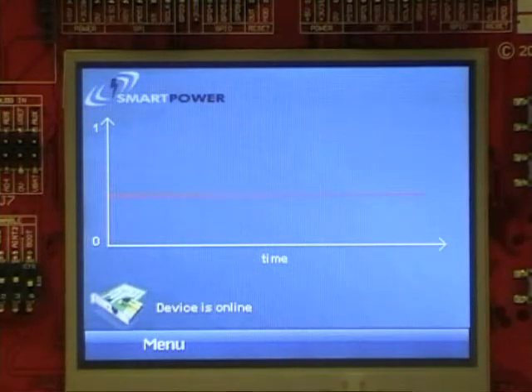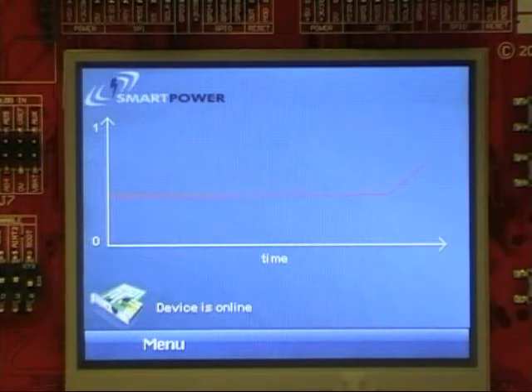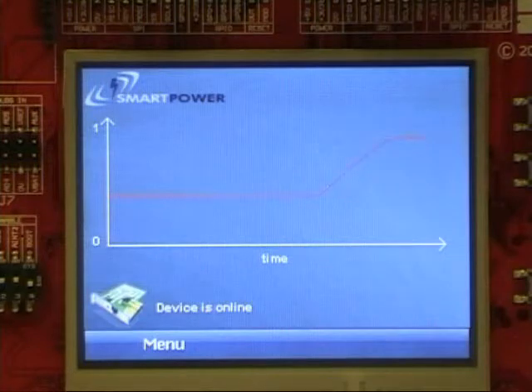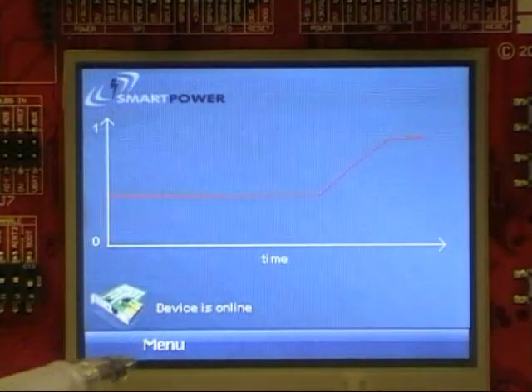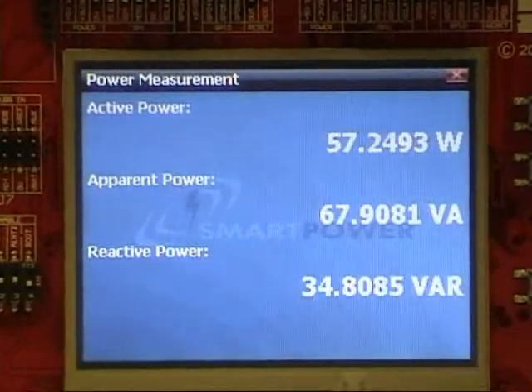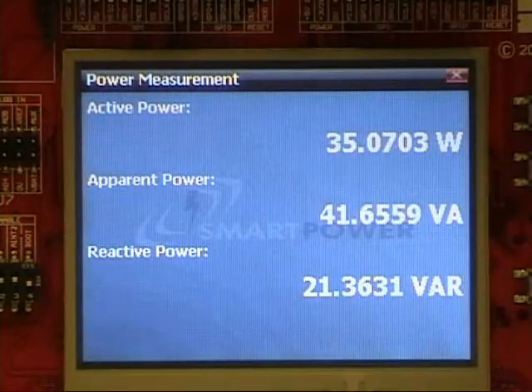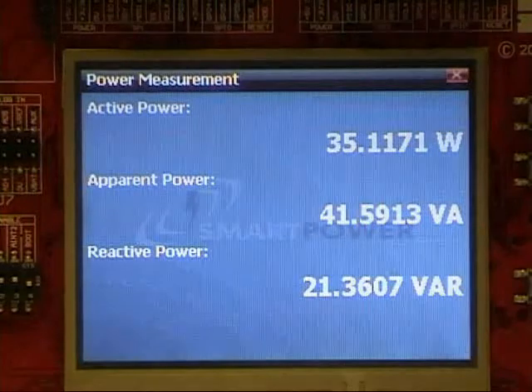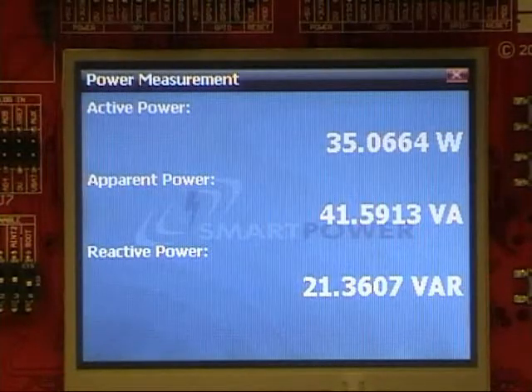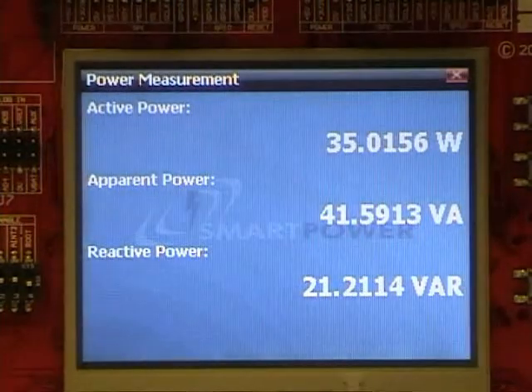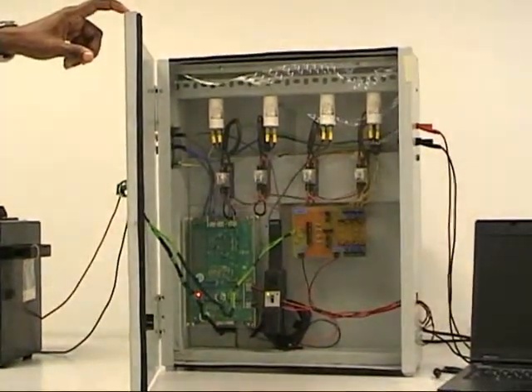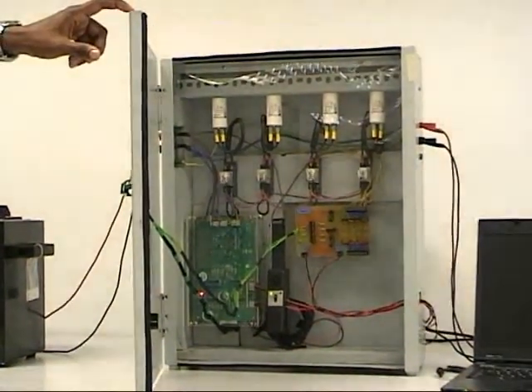As you can see from the graph, the power factor has improved. This is due to the fact that the power factor controller has automatically switched on a capacitor. Compared to the previous values of the reactive power, the current value is considerably reduced. When we look inside the device we can see that the first relay has been activated by the controller.